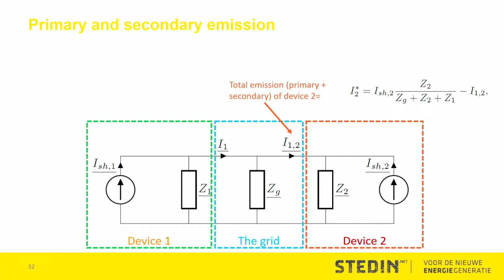It is the division of the current through the different impedances of the device itself, the grid, and the secondary device. That second device, if you measure at that point, will also show part of the emission from device 1. The emission flows through the internal resistance to the network, but also to the secondary device, so measuring at device 2 you will see the emission of device 1, and you can't distinguish between both. To make it even more complex, if device 2 is also a source of disturbances, measuring here you will always see the combination of both parts, the whole equation. This is an equation with more unknowns than number of equations, so it's impossible to solve mathematically.